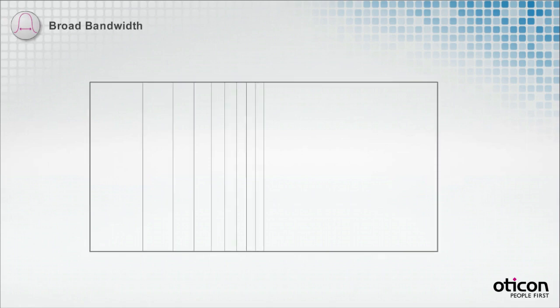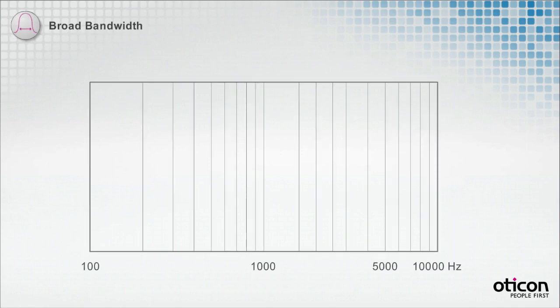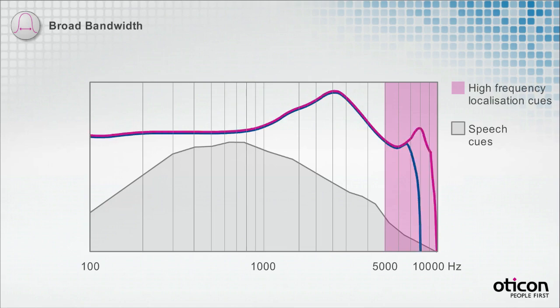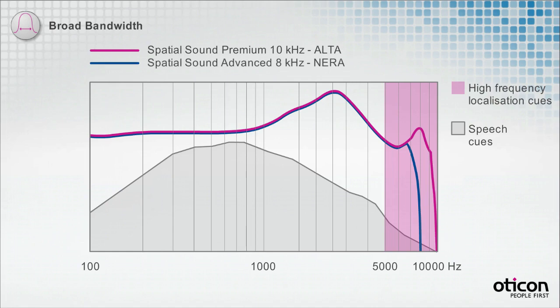With the broad bandwidths in both Alta and Nera instruments, Spatial Sound allows for the support of inter-aural differences across a broad spectrum. While both solutions preserve many of the vital spatial cues, the premium version, due to the extended bandwidth, will preserve more than the advanced version. Since there will be more inter-aural level differences to distinguish between, the premium user will simply have more cues to localize the surrounding sounds by.